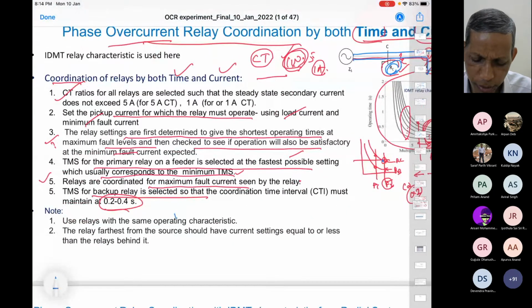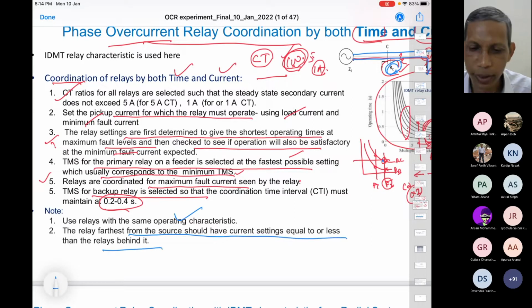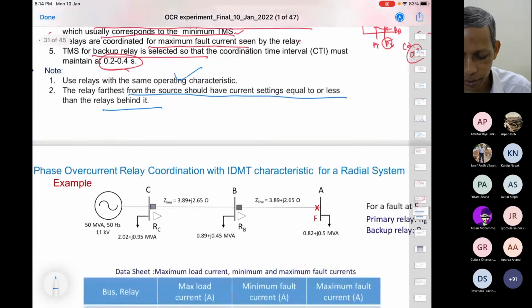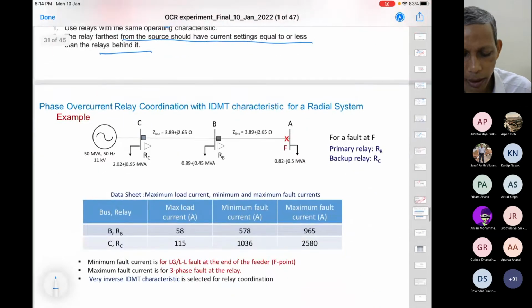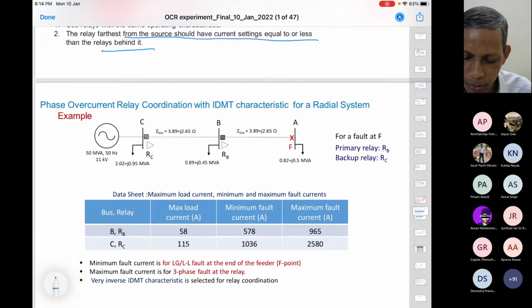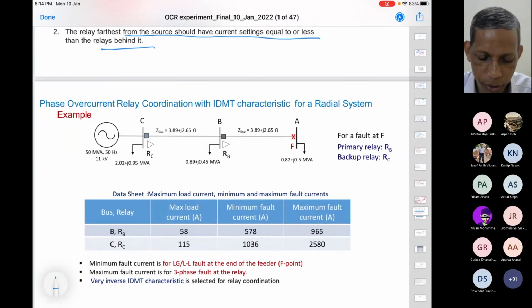So you can say same operating current, not to lead to confusion. The relay farthest from the source should have the current setting equal to or less than the relay behind it. This is a guideline from that perspective. We'll see an example, and then I think we are converging to something, and then we'll go to the laboratory testing. Phase overcurrent relay coordination, IDMT characteristic in a radial system.